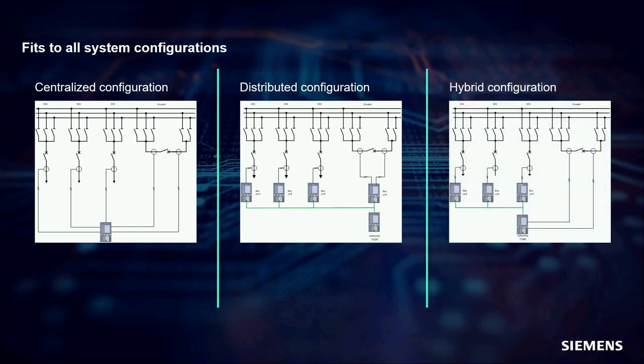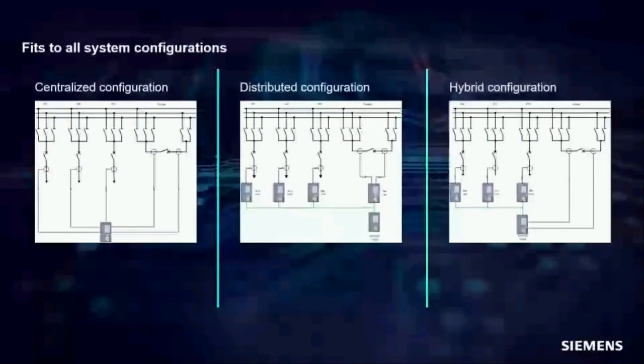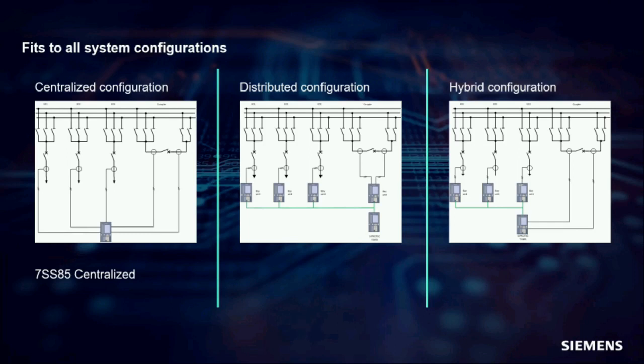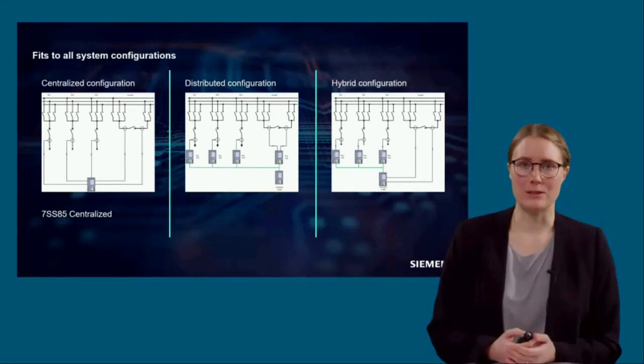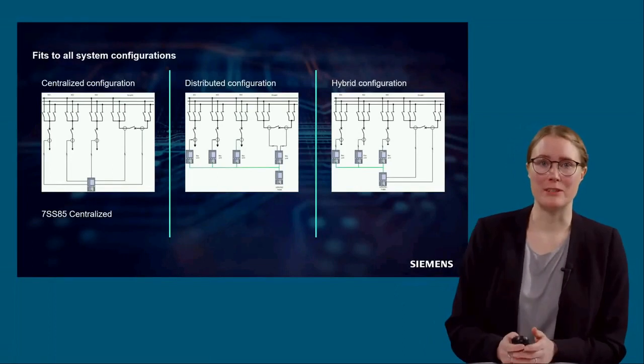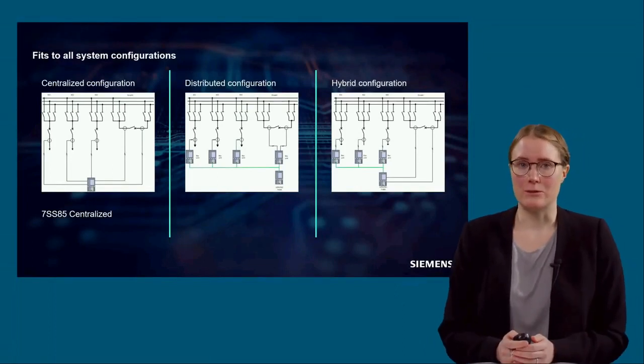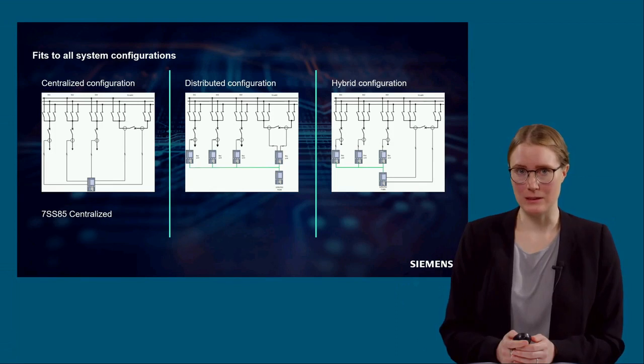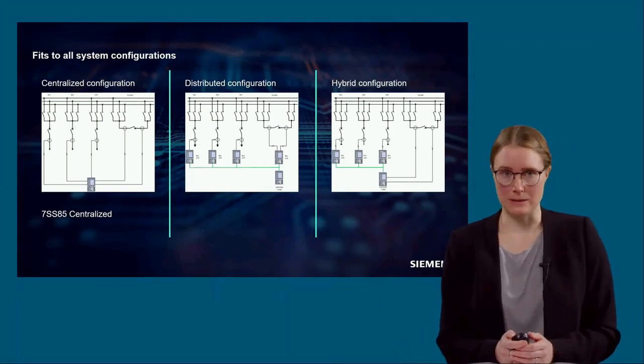Or you realize a hybrid configuration, where some data is collected by merging units and some of the process signals are directly wired to the 7SS85. So from the small switchgear with a compact design, for example a gas-insulated switchgear, to the large air-insulated system with like 40 bays, triple busbar with transfer bus and up to 10 bus zones, all are possible with the 7SS85. One device for all configurations, but of course the solutions themselves are different.